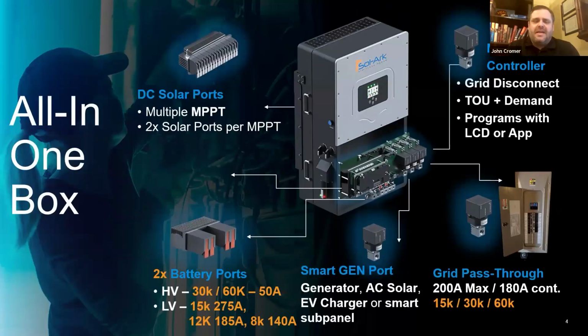Our specialty is making an all-in-one hybrid inverter. And really, Sol-Ark is, I call it, the pioneer of hybrid inverters. And yes, there were hybrid inverters before Sol-Ark, but actually the definition of hybrid inverter changed with Sol-Ark's product leadership. Before then, a hybrid inverter was a battery-only inverter. And now when you go to the trade shows and you look up hybrid inverters, they're all solar plus batteries. Sol-Ark was at the very front of that trend back in 2018. Prior to that, we were experimenting in off-grid and making off-grid systems easier, which led us to develop the 8K hybrid inverter. So what is a hybrid inverter?